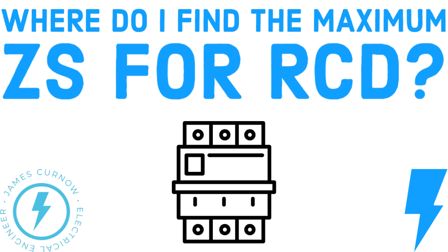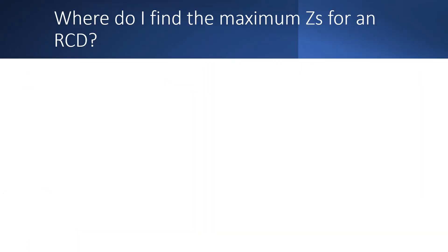Hi everyone and welcome to my channel. The question in this video is: where do I find the maximum ZS when using an RCD? So if you're working on an installation where you need to rely on the 30 milliamp RCD protection to comply with the disconnection time, such as in a TT system, what value should you enter in the column for the maximum permitted ZS?